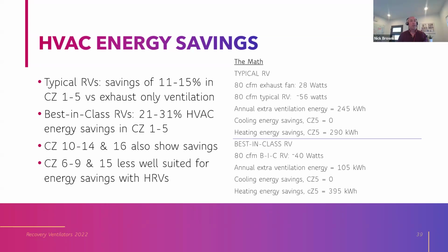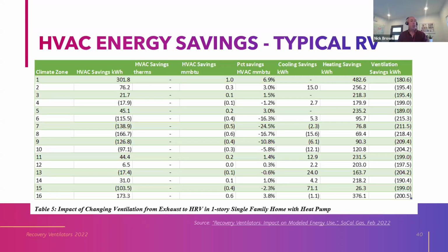Now, a best-in-class recovery ventilator, let's say, moves the same 80 CFM, but only uses 40 watts. Well, that cuts the extra ventilation energy down to 105 kilowatt hours. And by virtue of having a more efficient heat recovery core with a higher recovery effectiveness, now it's saving 395 kilowatt hours. So that's coming out quite a bit ahead, 290 kilowatt hours a year. See the difference?